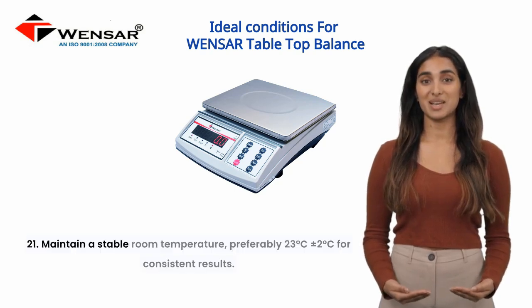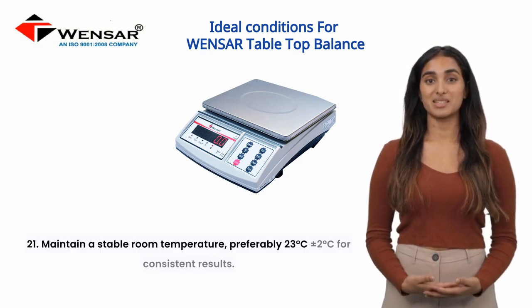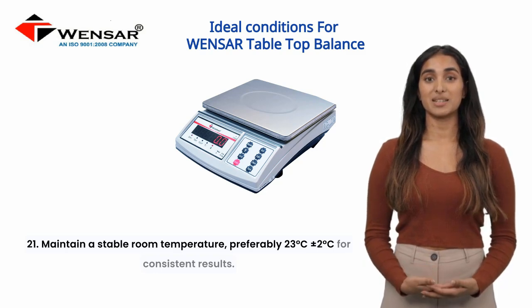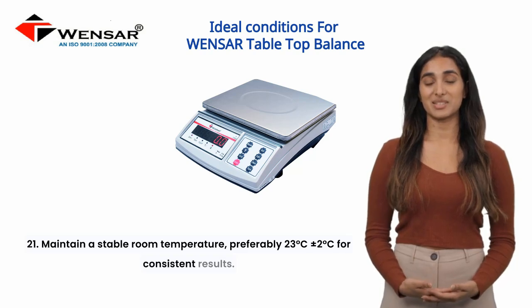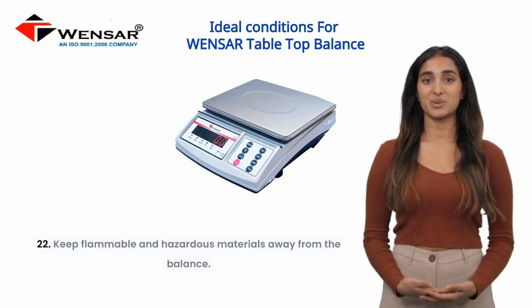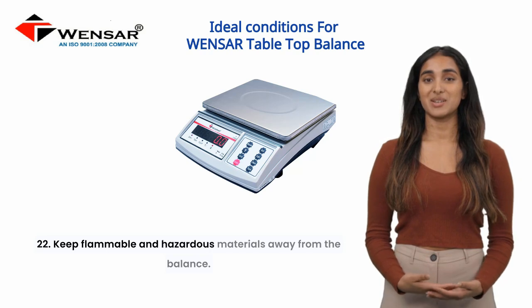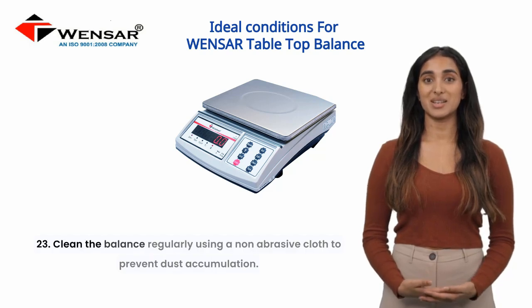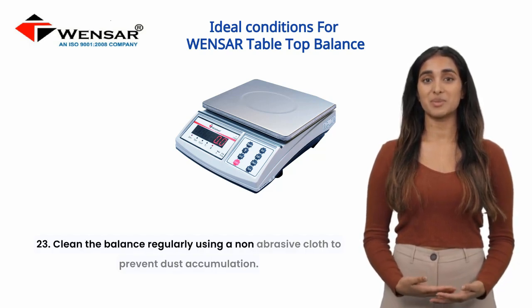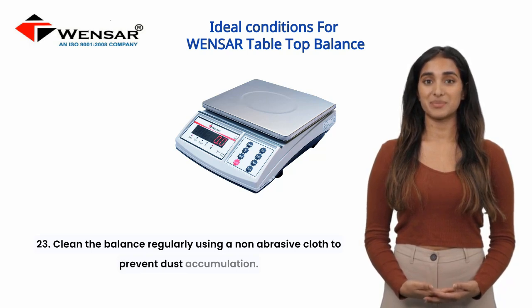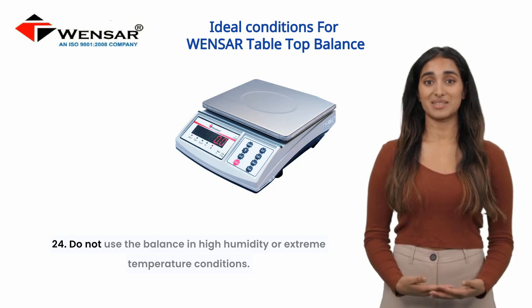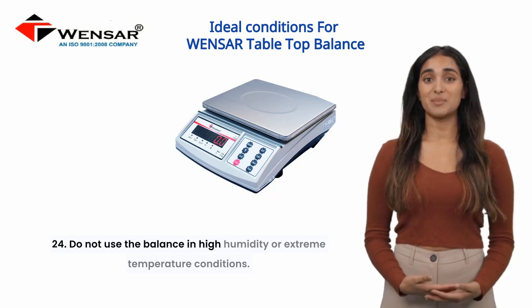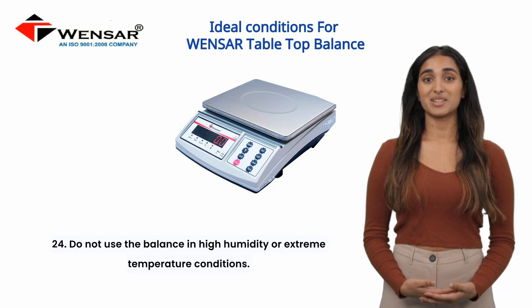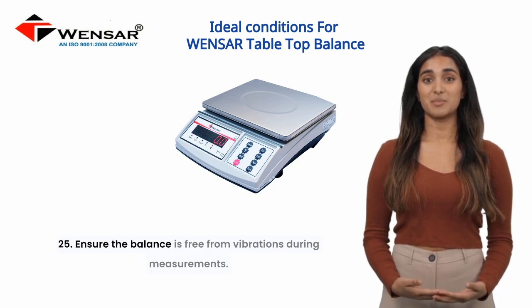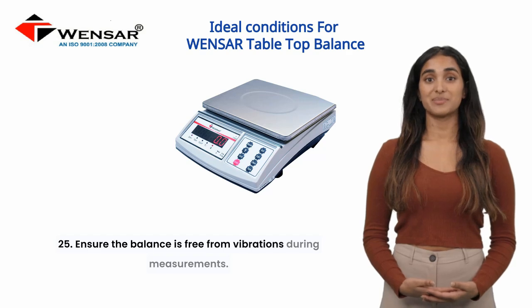21. Maintain a stable room temperature, preferably 23 degrees Celsius plus or minus 2 degrees Celsius, for consistent results. 22. Keep flammable and hazardous materials away from the balance. 23. Clean the balance regularly using a non-abrasive cloth to prevent dust accumulation. 24. Do not use the balance in high humidity or extreme temperature conditions. 25. Ensure the balance is free from vibrations during measurements.